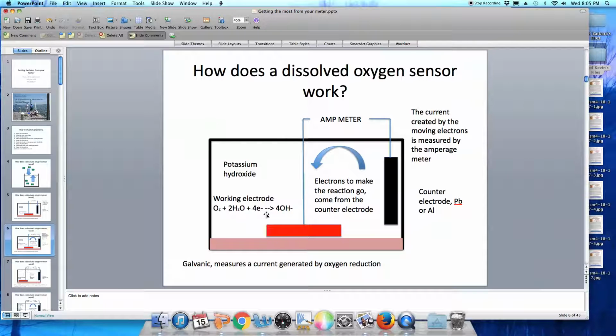So where do those electrons come from? These electrons are drawn from the counter electrode. They pass through an amperage meter, and the current created by these moving electrons is measured by the amperage meter, which then is translated into a dissolved oxygen value.